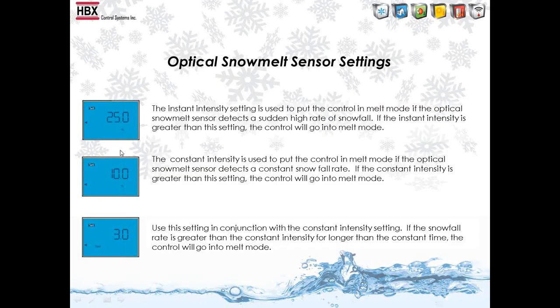Like we had talked a little bit before about the intensity settings. This is the instant intensity setting, and we could set this at anything from, I do believe, 5% as the minimum, all the way up to 90% or 80%. If you want it to react very quickly, you would set this at 5%. So if the snowfall rate goes over that 5%, then it will react and go out of idle mode and into melt mode. If you want the system to react a little bit slower, so you don't mind if it snows an inch or two before it turns on, you could set this anywhere from 30 to 60%.